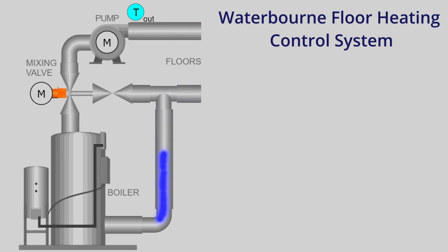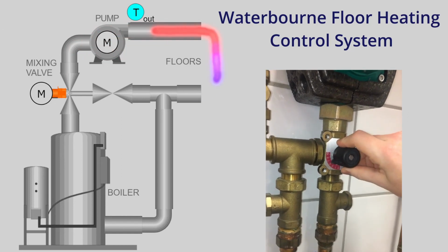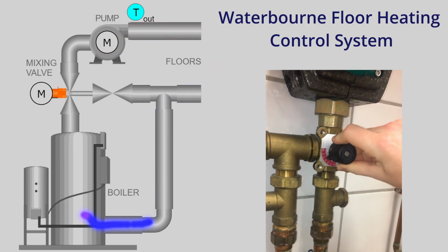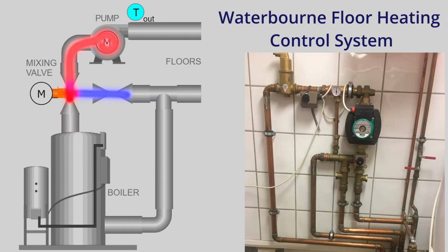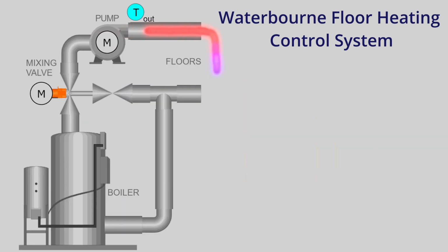A series of other valves adjust the flow of this mixed water into the individual rooms, giving regulation of temperature in each room. As of now, the mixing valve is manual, and the pump turns off only when the return pipe is warm enough to exceed the set point of the bimetal-based switch. A digital controller will provide better control and make it easier to add control features later on.